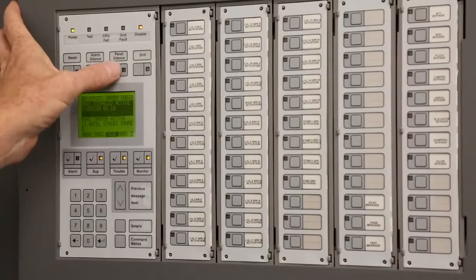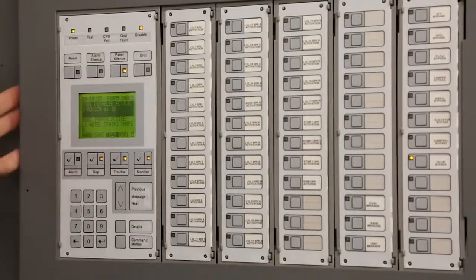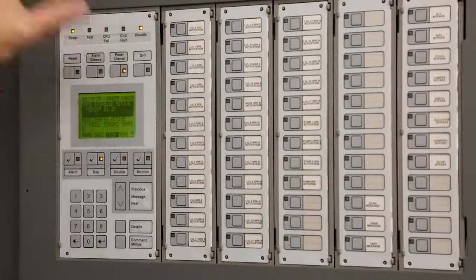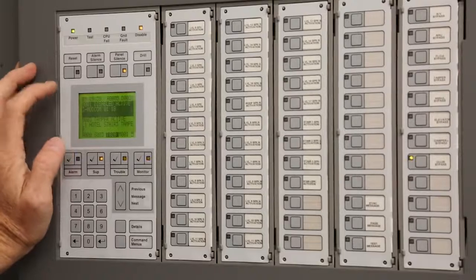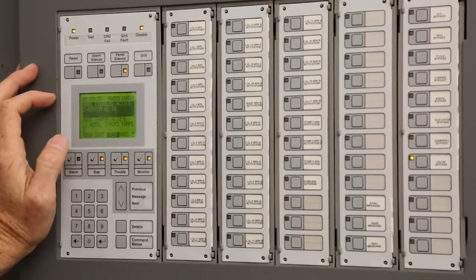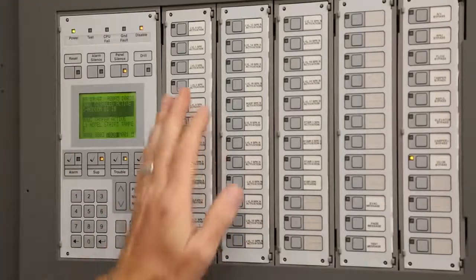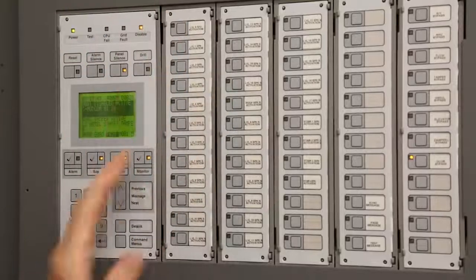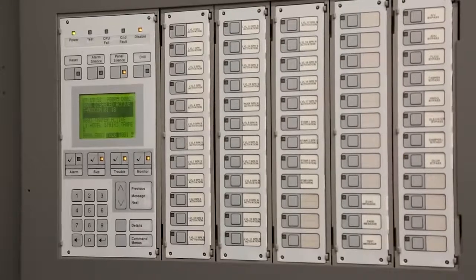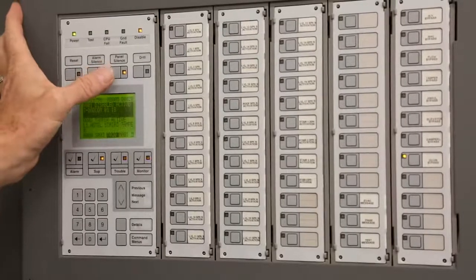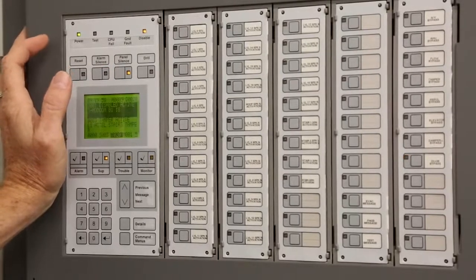We can hit panel silence here too. Panel silence basically shuts the panels up for the beeping because of the abnormal condition, and it will shut the local beeping up on any of these keyboards. This keyboard here is your main panel. We have a sub panel on the first floor north electrical room. They'll show the same display. Basically, just this portion right here will be shown over there. There are no bypass buttons or a microphone over there. But you have commands over there just like I'm doing here. You can silence it, you can reset and alarm silence from that location.